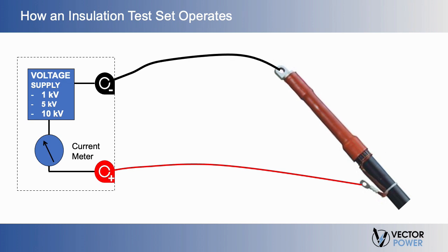For sound insulation, the resistance usually reads in the megohms or higher ranges. It is a high-range resistance meter or ohm meter with a built-in DC generator. The instrument's generator, which can be hand crank, battery, or line operated, develops a high DC voltage that causes several small currents to flow through and over the surfaces of the tested insulation. The ohm meter measures the total current and has an analog indicator scale, a digital readout, or both.